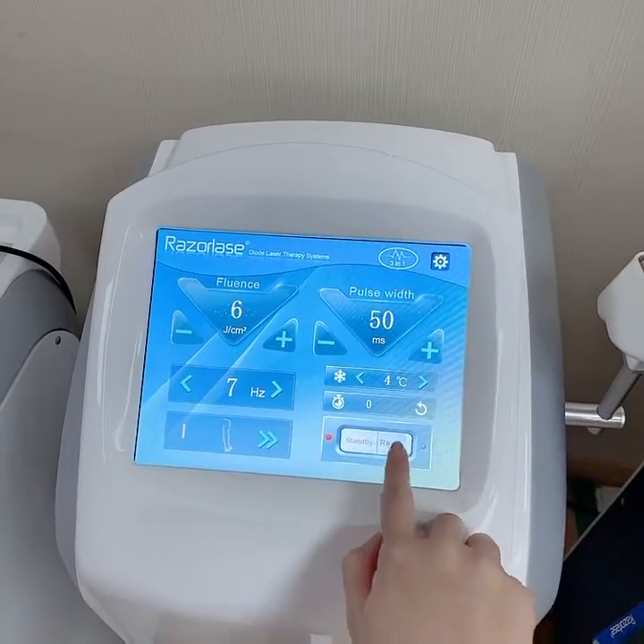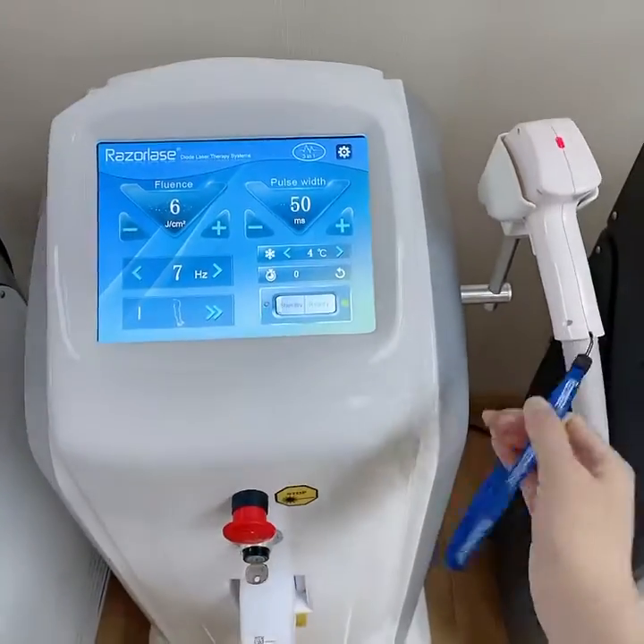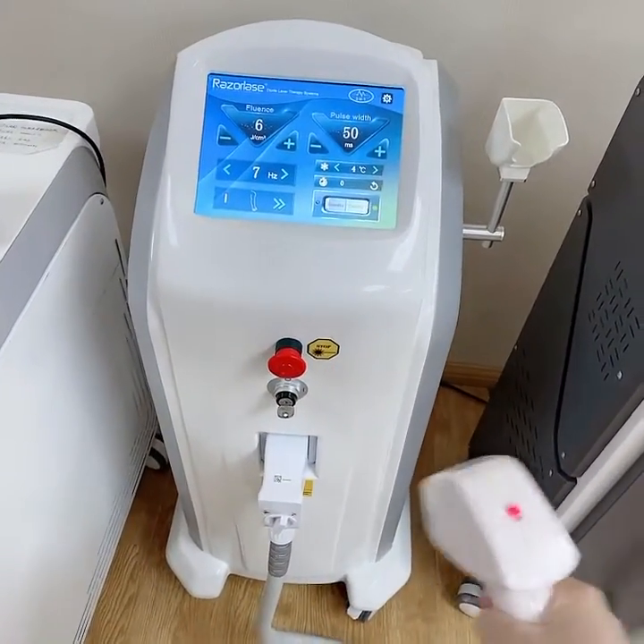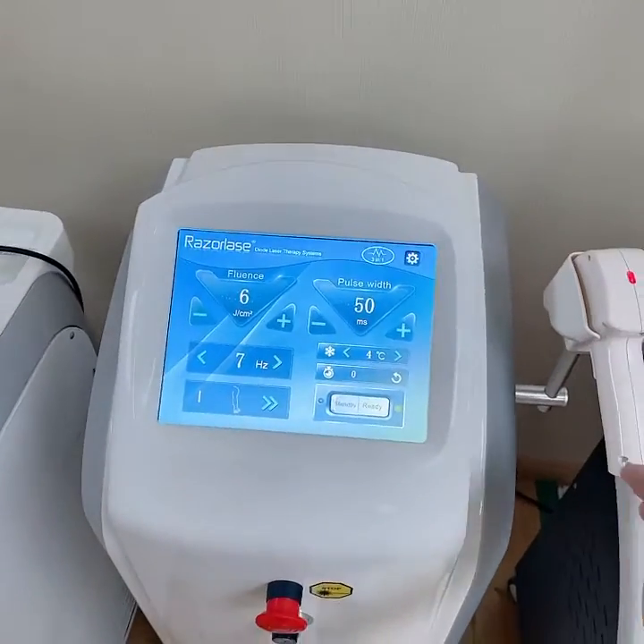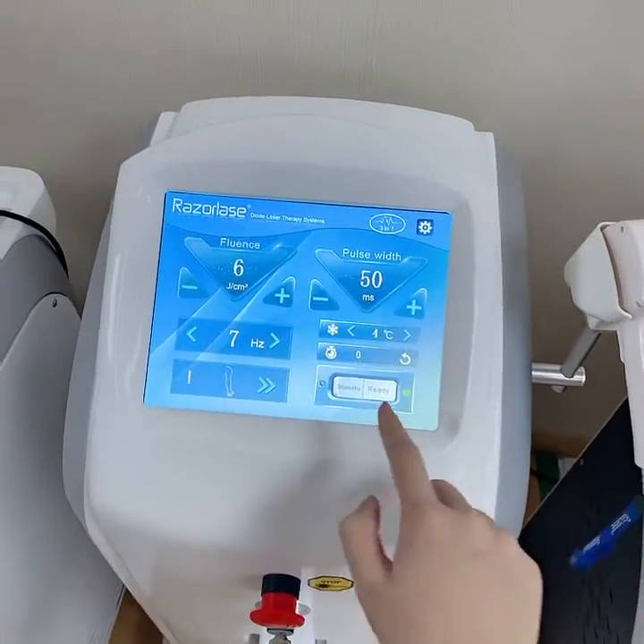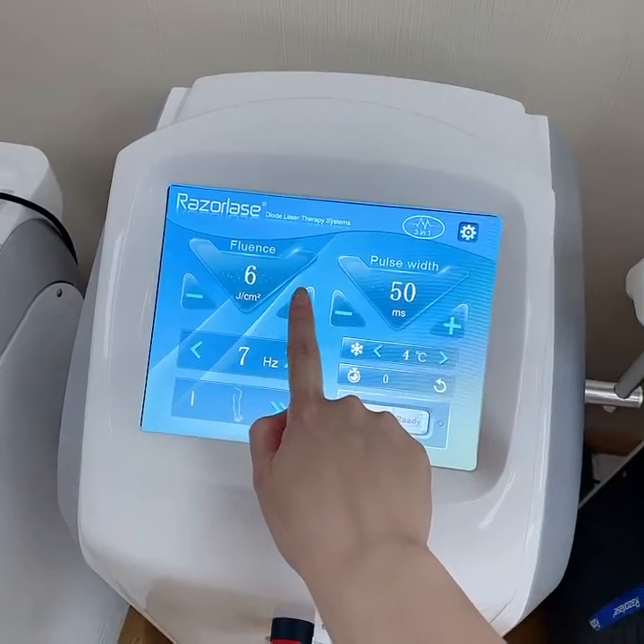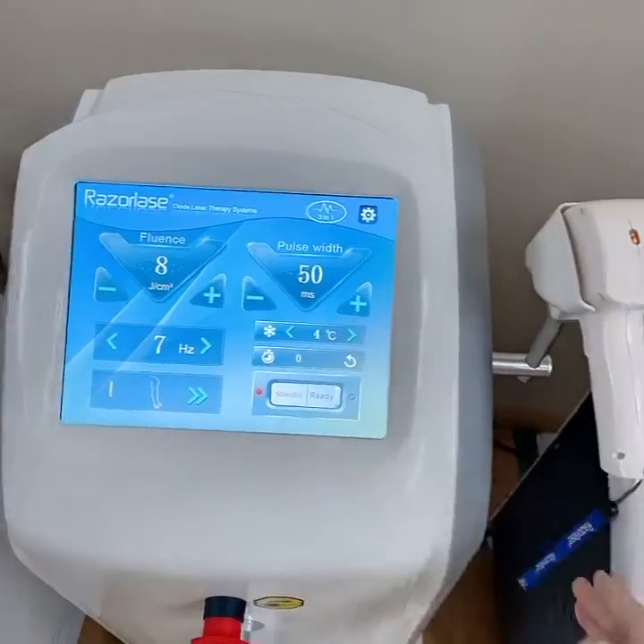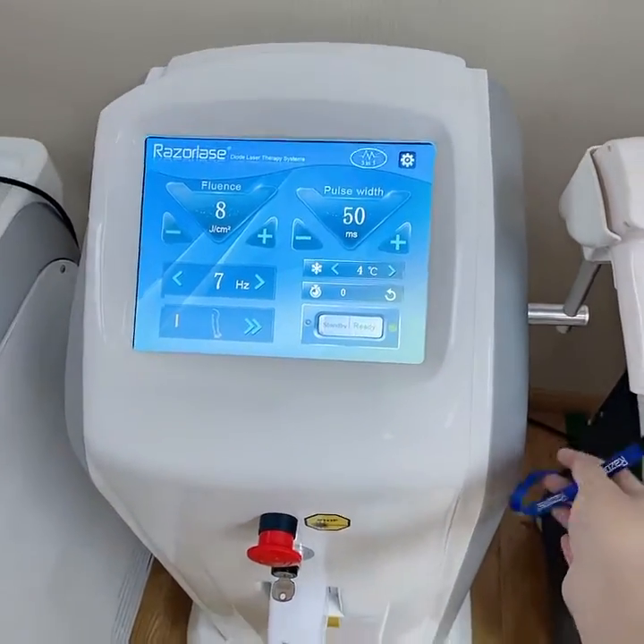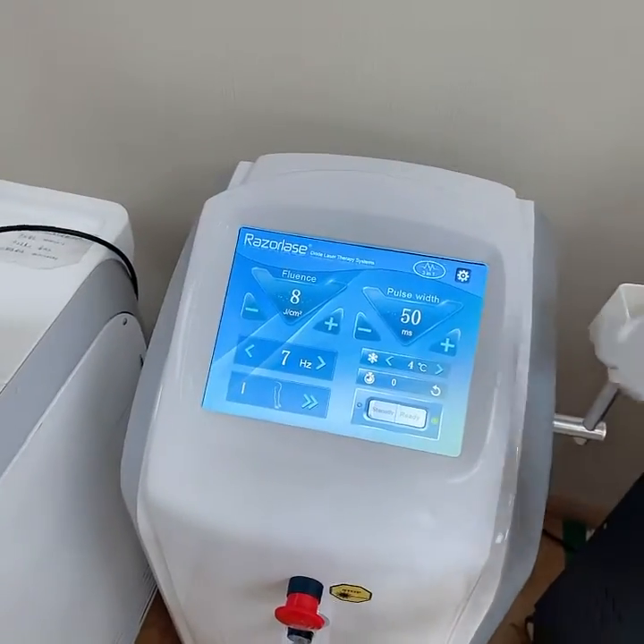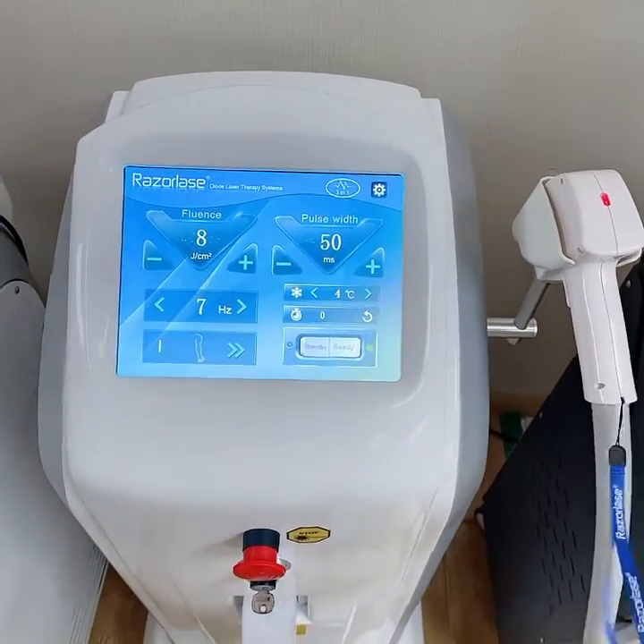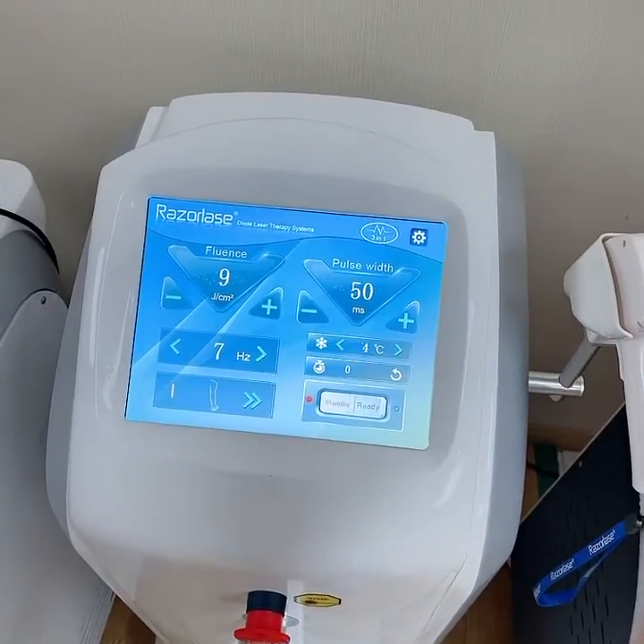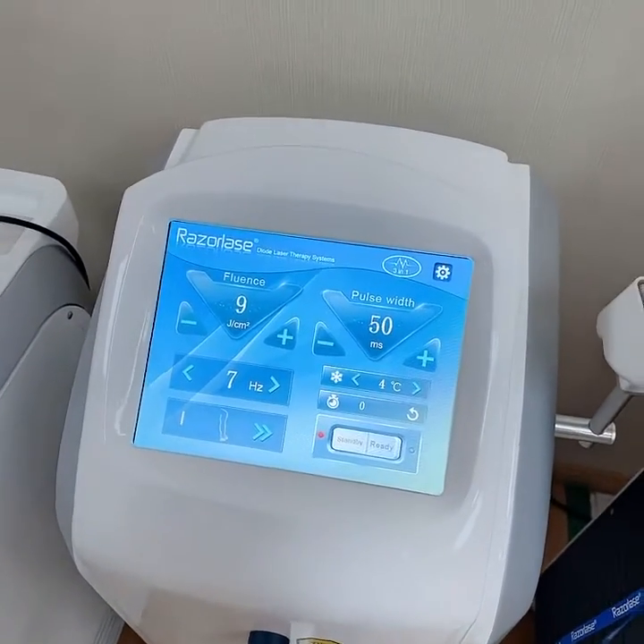Then, ready, and do skin test for a few seconds. Ask how the client feels. If the energy is not enough, increase the fluence one to two joules, then do skin test again. Ask how the client is feeling until the client feels a little warmer or a little pain. It will be the proper energy.